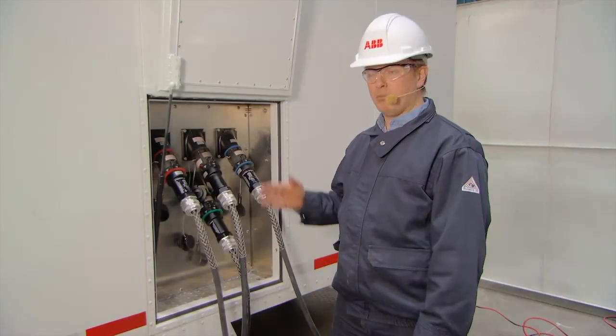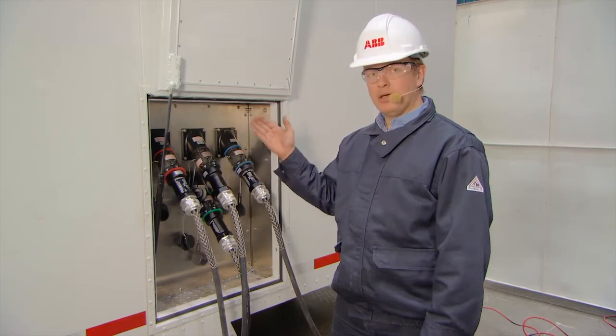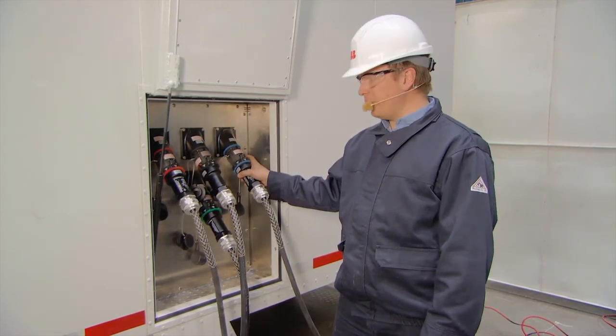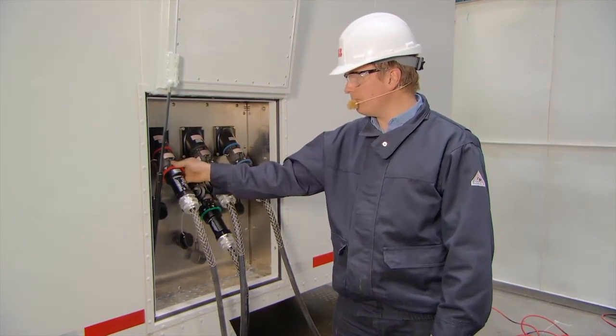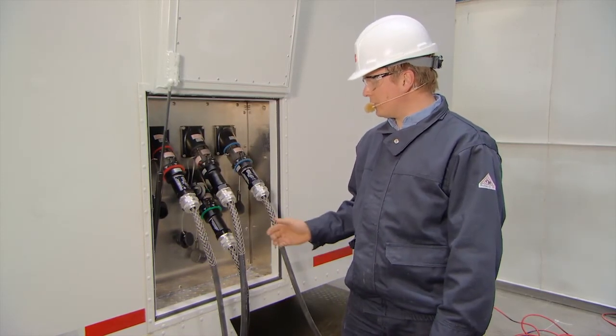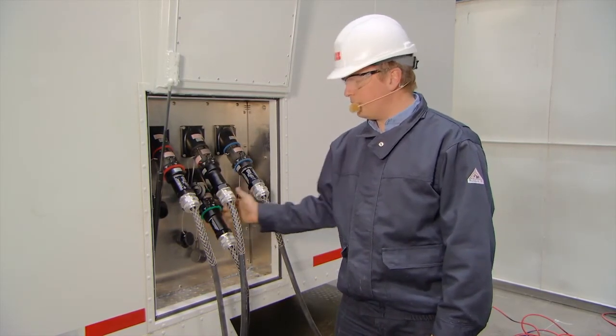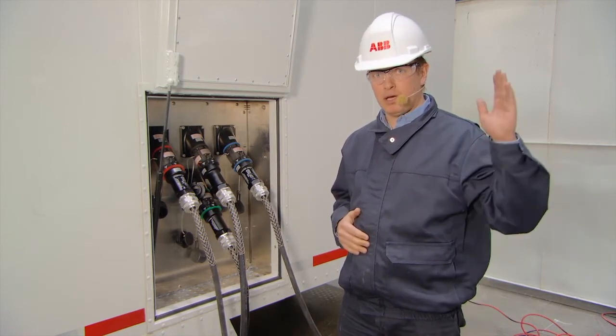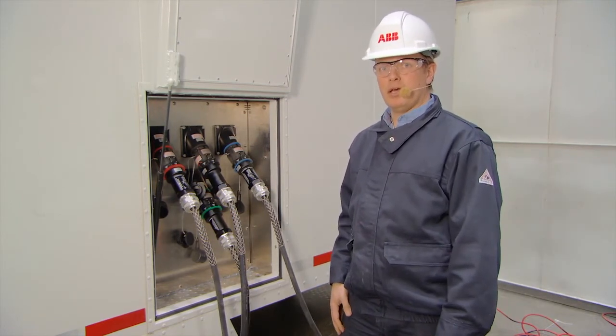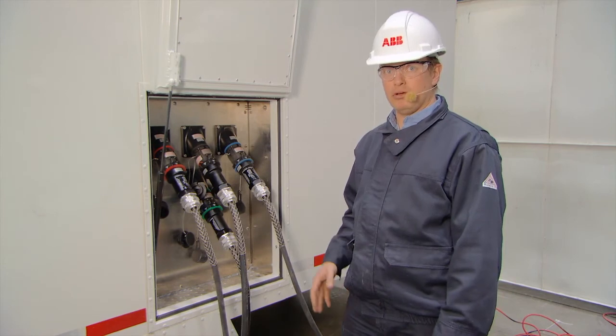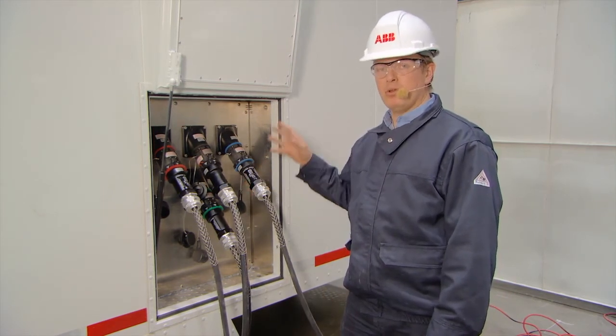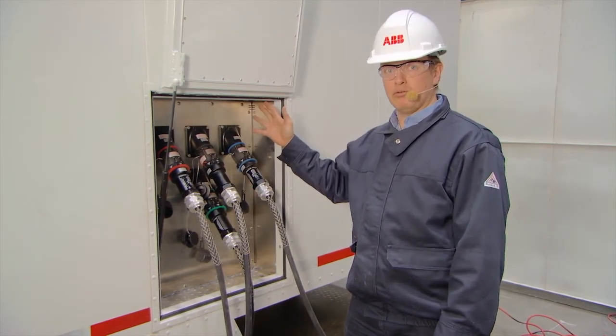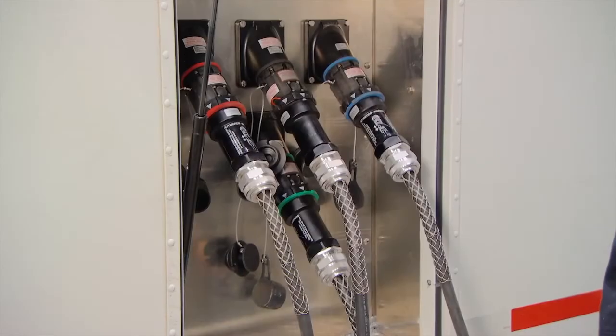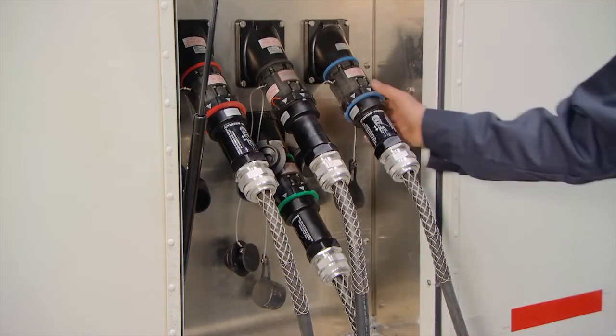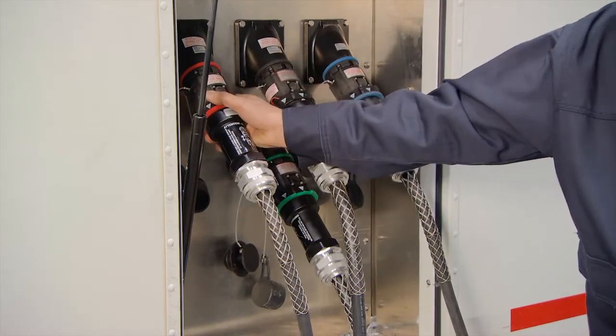Here is the main incoming power supply for the converter. It has 600 volt in 3 phases, 1, 2, 3, and it has a ground connection at the bottom. They should be matched to the power supply wherever you're coming from, and it should be ensured that you don't mix these power cables with the power cable on the other side of the trailer, which goes to the transformer. The 3 main incoming power cables, 1, 2 and 3, plus the ground power cable.